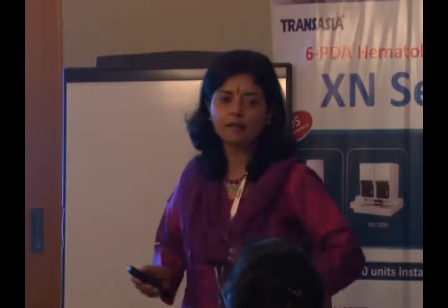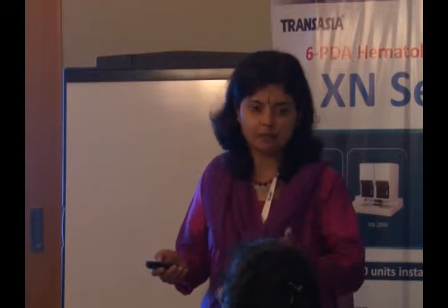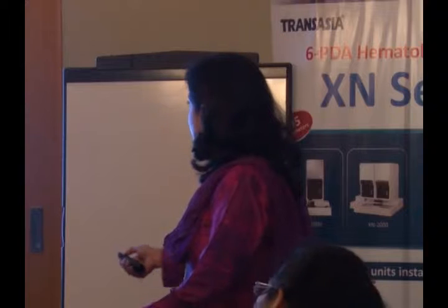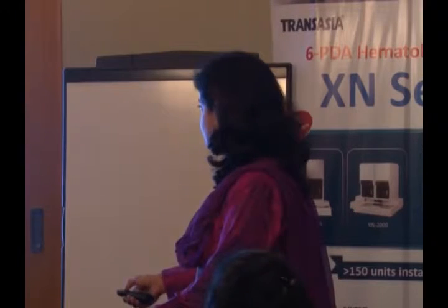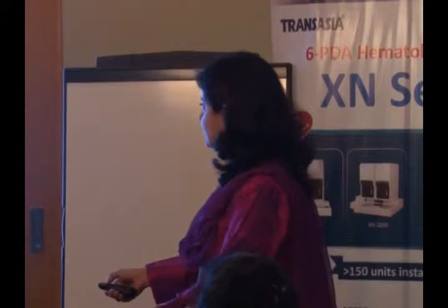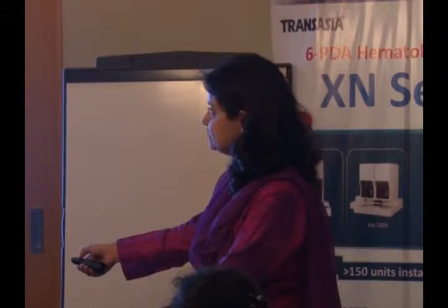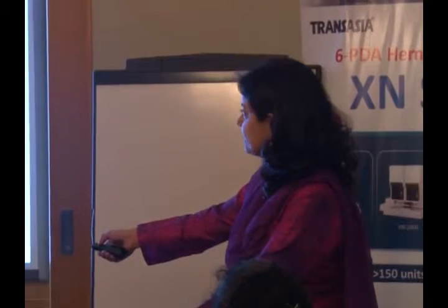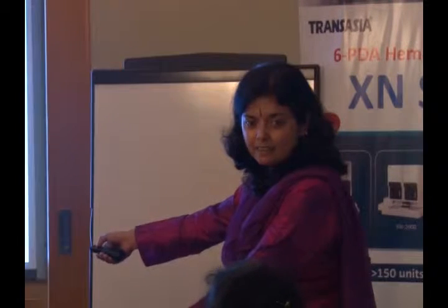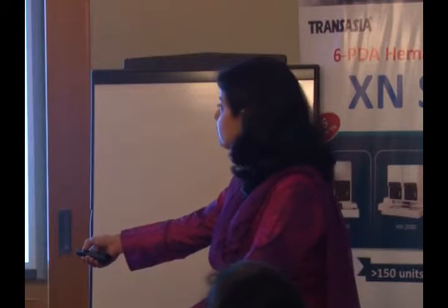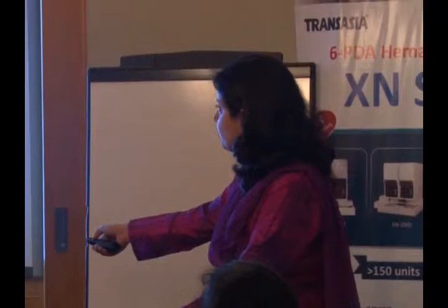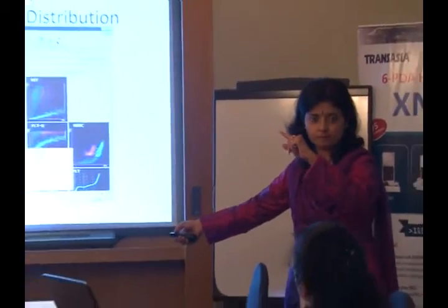Plateletcrit, till now I don't know what is the importance of plateletcrit. It's like hematocrit, but gives no importance. So when you have this kind of a clear thrombocytopenia, you see the platelet impedance is 60. Okay? You run it with optical, you get corrected. This is the platelet corrected, 140. So this is when the red channel is useful. When you have low platelets, see the large platelet here. The platelet optical is more specific. So the machine itself has that option to report both.